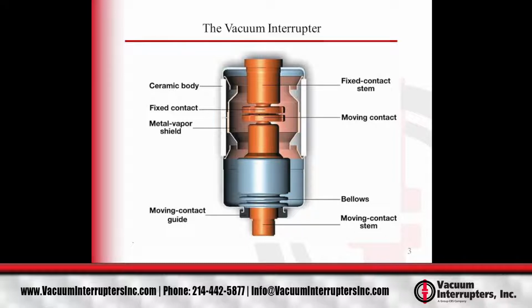This is a picture of a standard vacuum interrupter. You've got your fixed and moving copper shafts, and then ceramic insulating the two ends from one another. Inside you have a series of shields and the metal bellows as well. The purpose of the shields is to catch metal vapor when you interrupt current. If you open the contacts while current is flowing, then you will vaporize a small amount of that metal contact material, and you don't want that material depositing on the inside of the insulating material, because if that were to happen, then you could have an internal short circuit, which would eventually lead to failure.